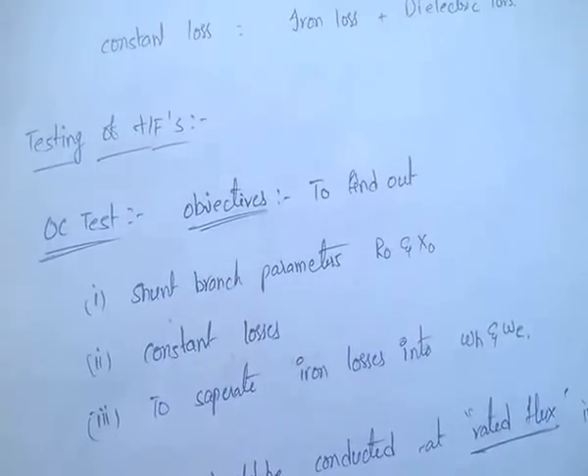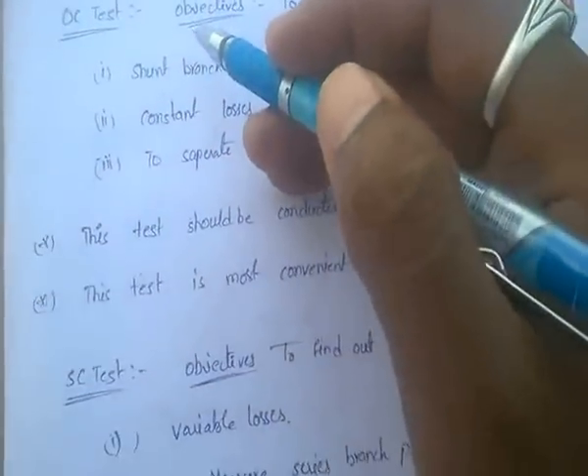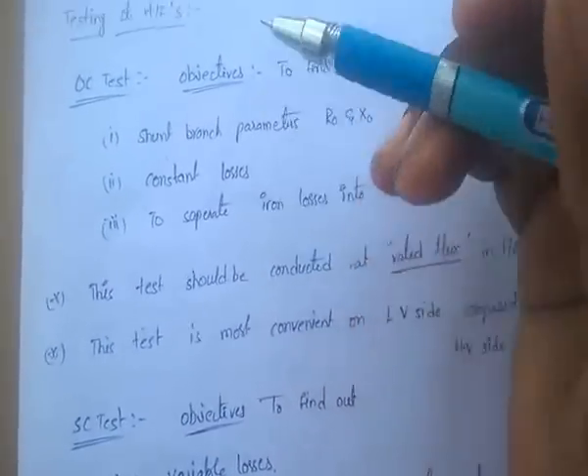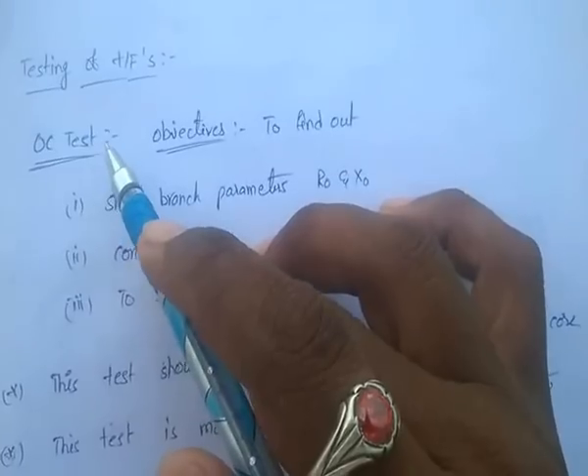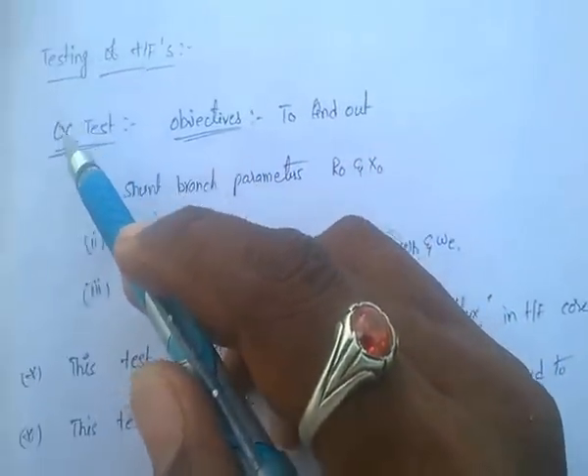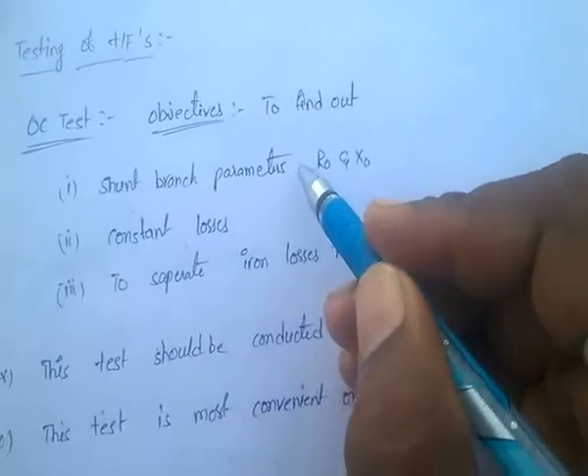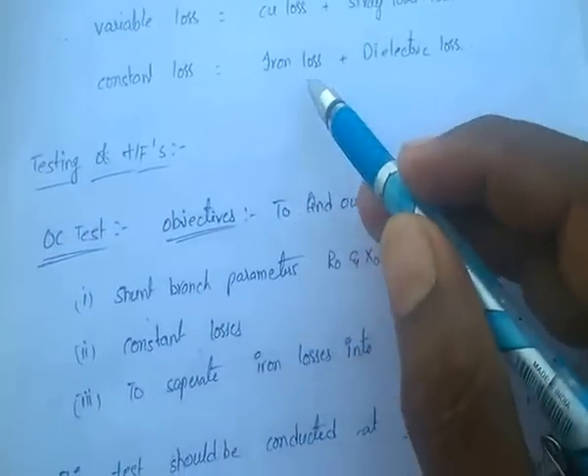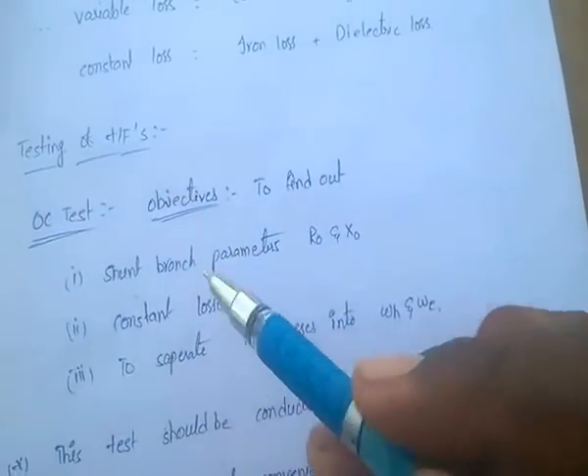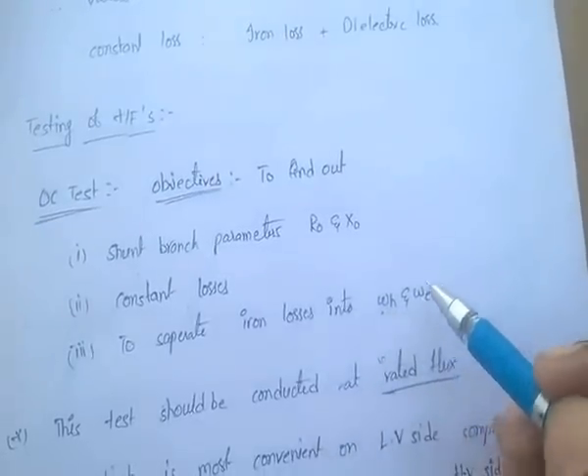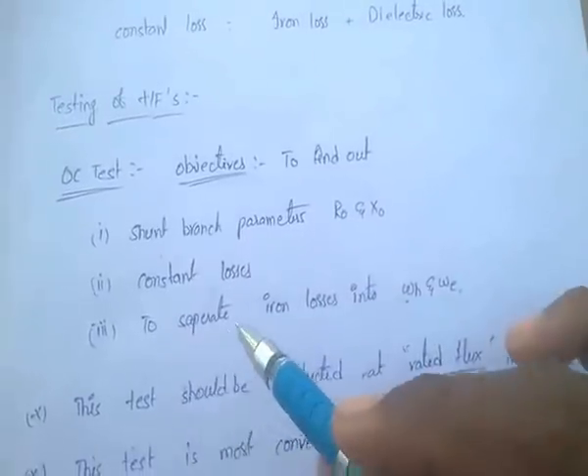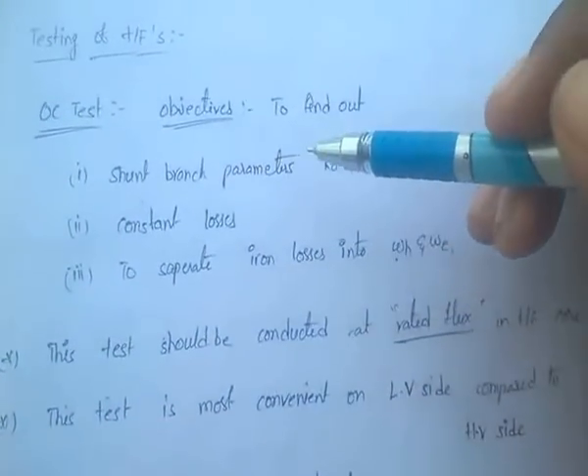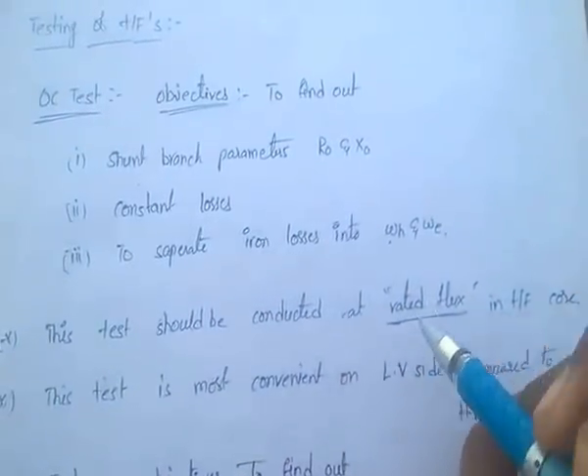Testing of transformers: OC test and SC test are conducted to find out the losses and performance of the transformer. The open circuit (OC) test objectives are: to find out the shunt branch parameters R0 and X0, to find out the constant losses (iron losses plus dielectric losses), and to separate iron losses into hysteresis losses (Wh) and eddy current losses (We). The OC test should be conducted at rated flux in the transformer core.